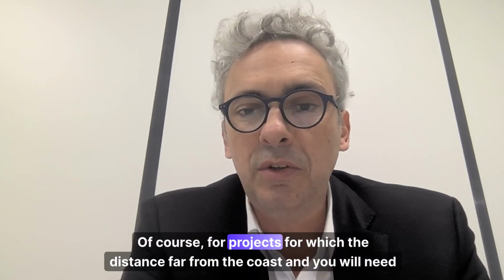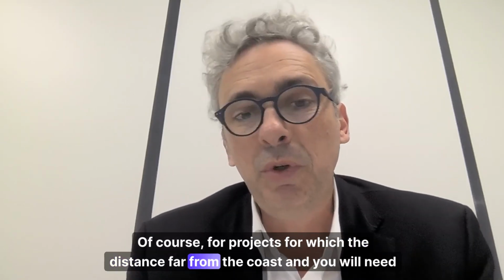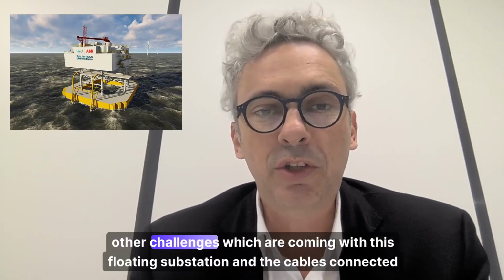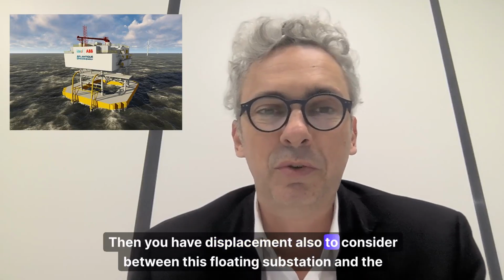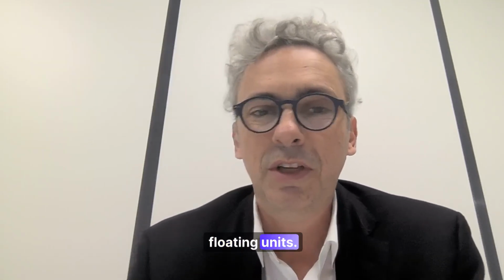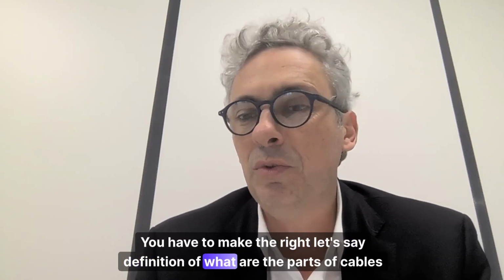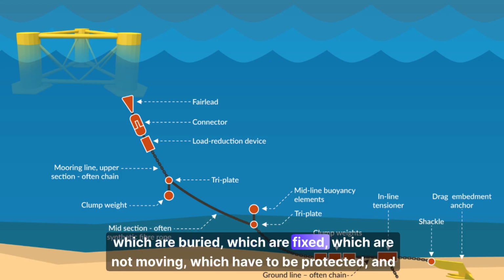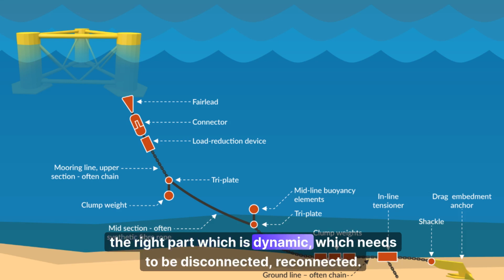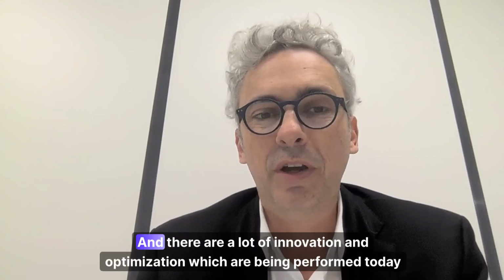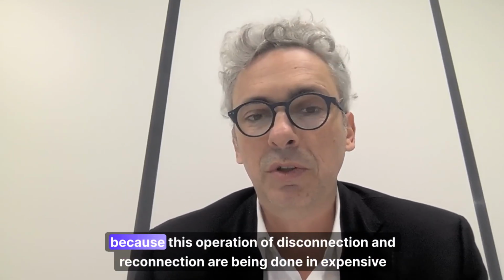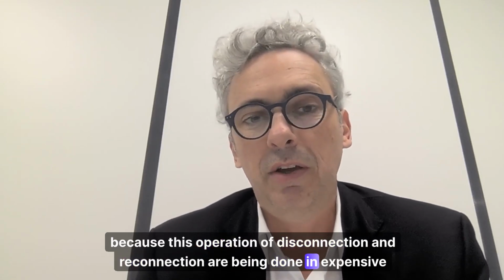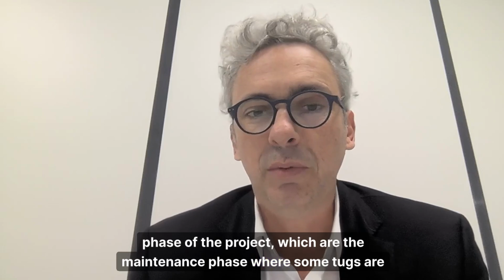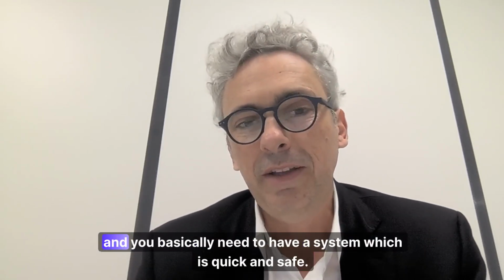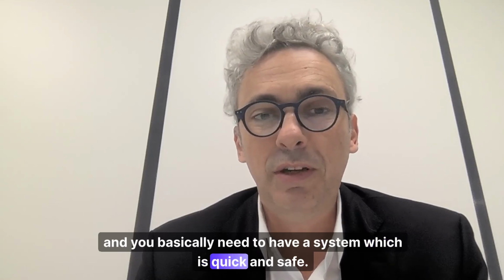Of course, for projects where the distance is far from the coast, you'll need a floating substation, and there are other challenges coming with this floating substation and the cables connected to it. You also have displacement to consider between the floating substation and the floating units. You have to make the right definition of which parts of the cables are buried, which are fixed and not moving and need to be protected, and which parts are dynamic and need to be disconnected and reconnected. There's a lot of innovation and optimization being performed today, because this disconnection and reconnection operation happens during an expensive phase of the project - the maintenance phase - where tugs are mobilized to stabilize the floating unit, so you need a system that is quick and safe.